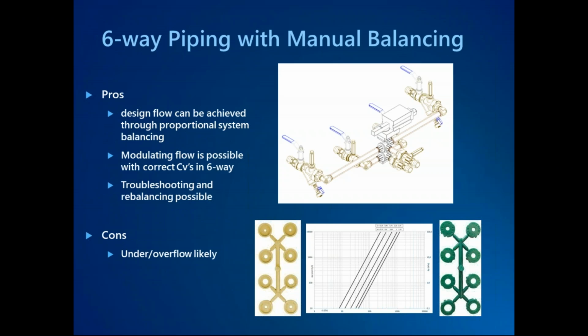So next up, manual balancing valve. It offers a little bit better flow control because we can actually go through and proportionally balance every single zone to meet the design flow. And troubleshooting is possible by going back and remeasuring and re-verifying flow. But again, unless we're doing reverse return piping, if we're trying to tie manual balancing valves in with a variable frequency drive system, a variable flow hydronic system, you're going to have issues with underflow and overflow. And that's just inherent to having a static balancing valve trying to interact with a dynamic pumping system.